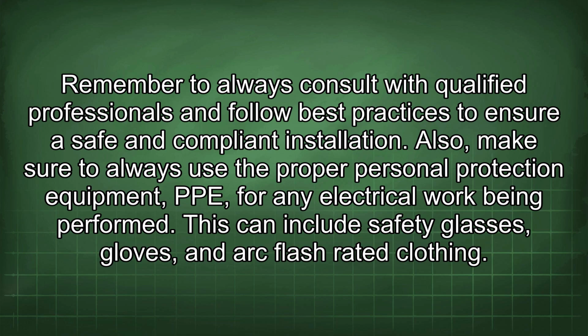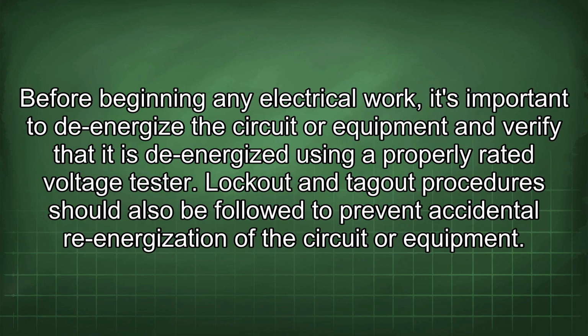Also, make sure to always use the proper personal protection equipment (PPE) for any electrical work being performed. This can include safety glasses, gloves, and arc flash-rated clothing. Before beginning any electrical work, it's important to de-energize the circuit or equipment and verify that it is de-energized using a properly rated voltage tester. Lockout and tagout procedures should also be followed to prevent accidental re-energization of the circuit or equipment.